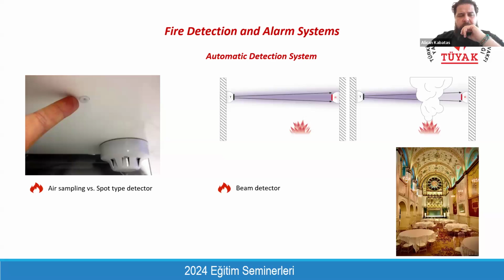And also, another alternative to these physical detectors is generally used in this kind of wooden buildings. Instead of having spot type detectors, you can use this air sampling type, which is much smaller than the spot type detector. Or you can use these beam detectors, or call them OSID detectors. You only have transmitters and receivers on the walls, and you will not see any equipment on the wall or on the ceiling. If you will be responsible for renovation or refurbishment of historical buildings, or you have a very challenging architectural ceiling design, instead of spot type detectors, you can suggest that the electrical designer use air sampling or beam detectors.